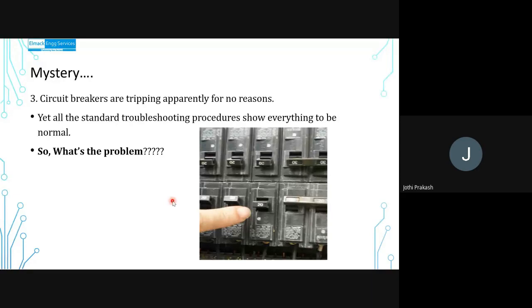The third mystery was a little more common to every industry: circuit breakers are tripping, apparently with no reason. The circuit breakers are rated correctly for their load, but they are tripping. They trip often, but people couldn't find the problem with their standard troubleshooting techniques, like using a multimeter or a current clamp meter. It showed everything was normal, but they couldn't find what was causing the circuit breakers to trip. These mysteries happened earlier, in the 1990s.